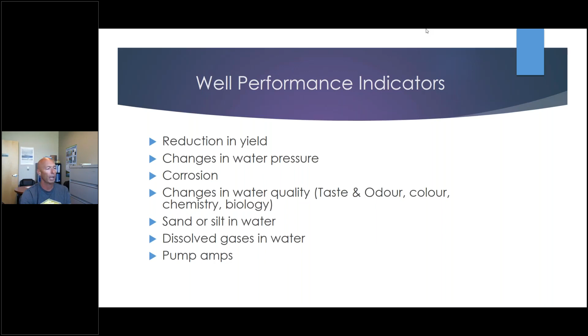So the failing of the well, basically the structure failing, which is the casing or screen. We don't see the screen fail too much, but we definitely see the casing fall apart. Pumps break down. Are we changing these pumps way too often? That's a big one. Is there a problem that's been overlooked? Over pumping, excessive drawdown, as I was saying before. We're always going to get that cone of depression, but we don't want to go past that. Aquifer depletion, well interference from another well, incrustation, corrosion, the fouling, which is biofouling, possibly manganese or iron. Sand or silt coming through the well that didn't show up when the well was drilled. Then again, contamination, and then watch, like I said, shortening of equipment life.